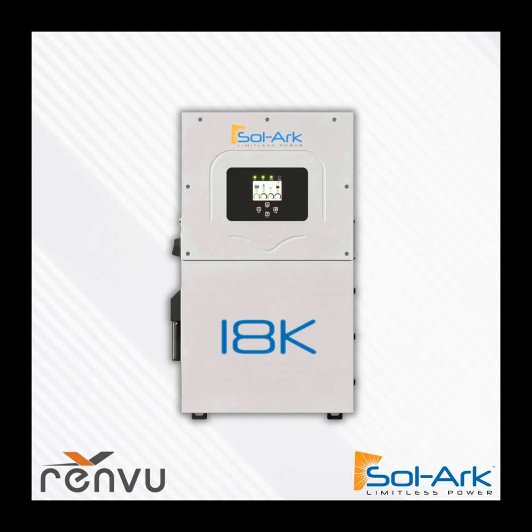The gen port -- this is something I just recently learned -- the relay on the gen port is larger than on the 15K as well. I don't know if we've updated our manual to reflect that, but I believe that will resolve issues for customers who buy, say, a 22 kilowatt stationary generator and want to actually run it at 22 kilowatts. The gen port on the Sol-Ark used to clip at 19 kilowatts and would shut off if you went above that. I'm not sure what our software constraint is now, but I know the relay is larger, so there's a possibility the gen port capacity is a bit larger than in our initial product documentation.